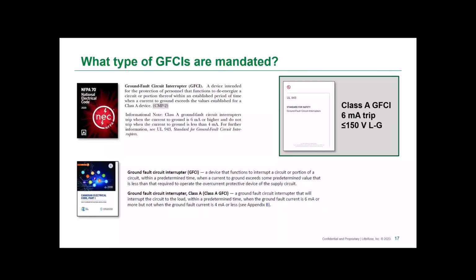So the GFCIs that have been specified in the codes, which have done a great job of reducing those electrocutions, especially in the home, were all Class A GFCIs. And up until the 2020 version of the NEC, the definition of GFCI was a Class A device that tripped at 6 milliamps based on UL 943.